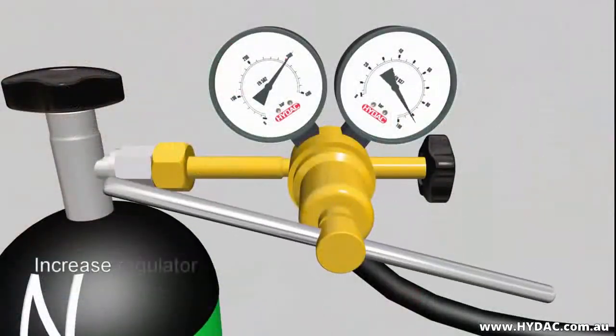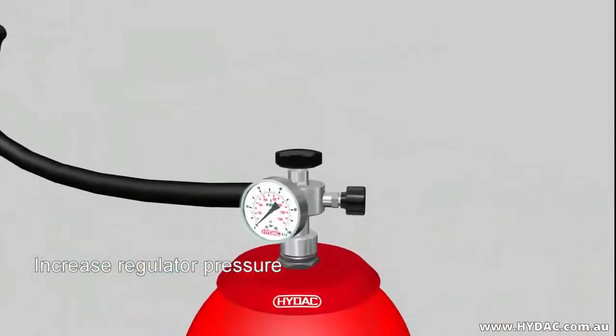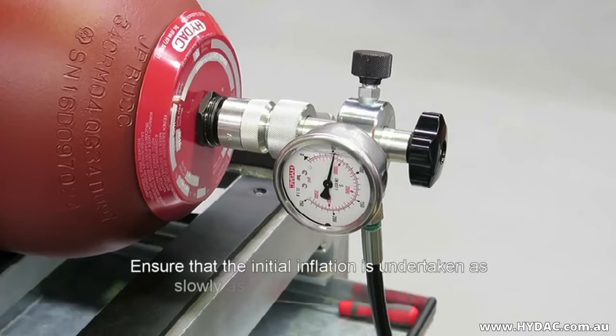Begin the gas flow from the bottle to the accumulator by slowly raising the pressure at the regulator. When shipped, the majority of HYDAC bladder accumulators are charged to 2 bar. At this pressure the bladder is inflated and is in contact with the inside of the shell, and there is little chance of damaging the bladder. However, if the bladder is new or has been deflated, you must ensure that the initial inflation is undertaken as slowly as possible — otherwise the bladder may stretch too quickly and rupture.